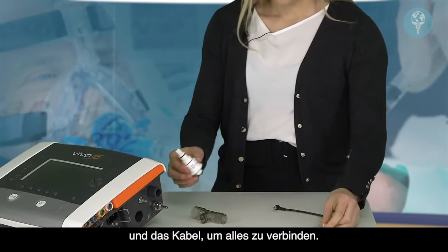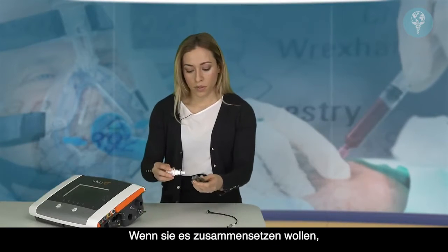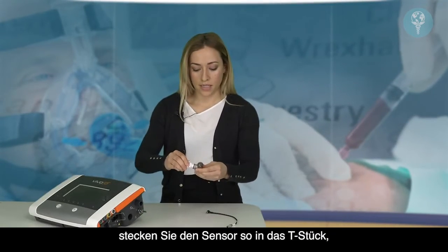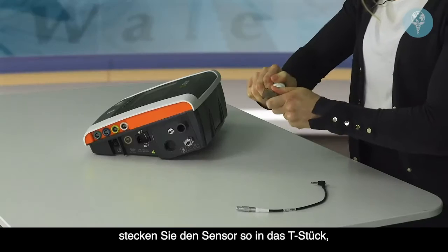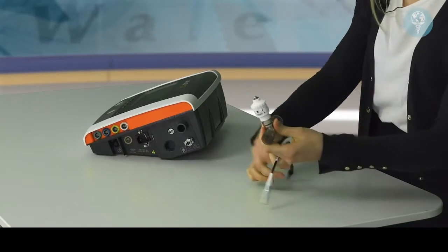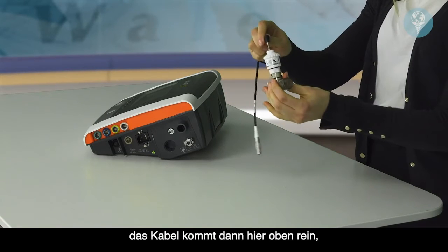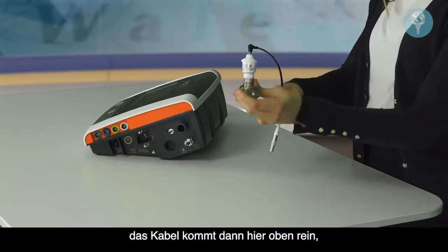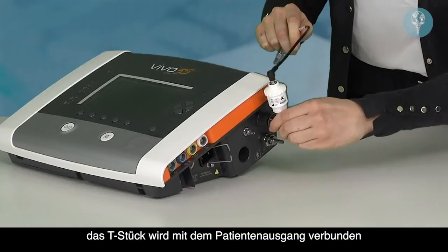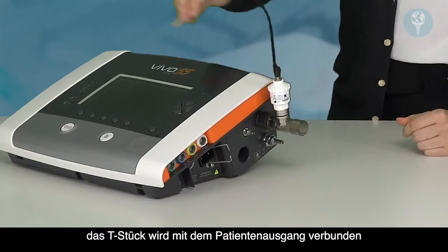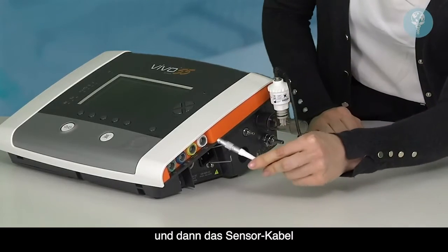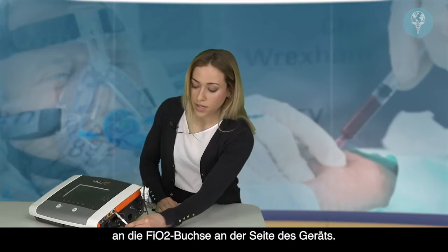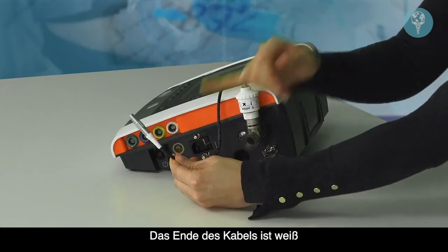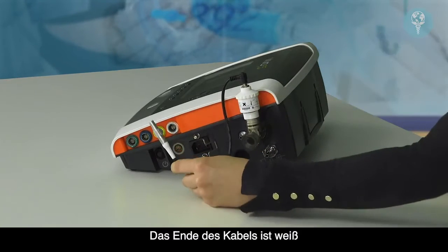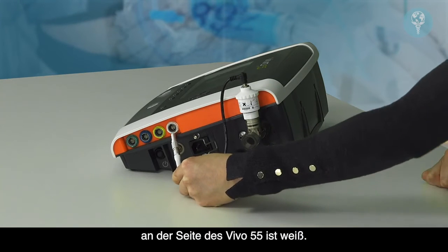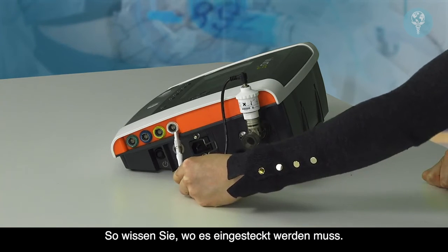When you first get them to put them together, put the sensor into the top of the T-piece like that. The cable then goes into the top here. The T-piece then connects to the patient outlet there, and then we attach the sensor cable into the FiO2 socket on the side of the device. The end of the cable is coloured white here, and it lines up with the white outlet on the side of the Vivo 65, so you know which one to plug in.